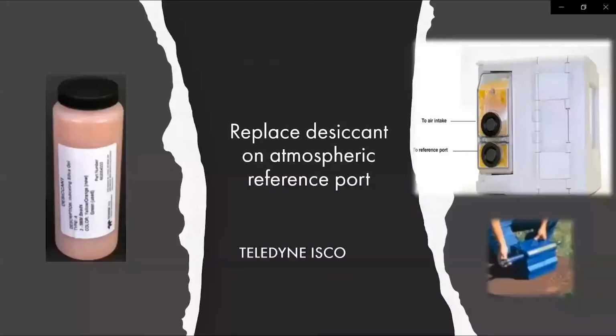So the first thing I would do when I see data like that going below zero is replace the desiccant, because the sensors have a reference to atmosphere. And if your desiccant is old or damp and it's no longer able to essentially breathe, you're going to cause that type of drifting. So it's usually quick, easy maintenance to replace your desiccant.